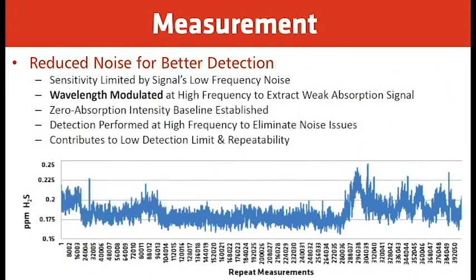All right. In order to improve the sensitivity of our analyzer, we're also using a fairly common feature called wavelength modulation spectroscopy, or WMS. It is based on the modulation of the light emitted by the laser that is slowly tuned through an absorption feature of the species that we are going to detect. The interaction of the modulated light with the absorption feature can generate signals at different harmonics of the modulation frequency, which we can use for the analysis. So the whole idea, without going into too much detail, is that using wavelength modulation spectroscopy, we can get a very good signal-to-noise ratio. And that, combined with the other designs and features of our system, for example the vacuum pump, as well as the long-path cell, gives us the opportunity to do a very good low detection limit measurement with great accuracy.